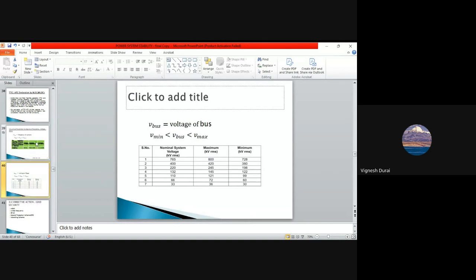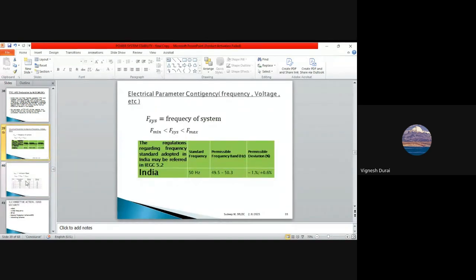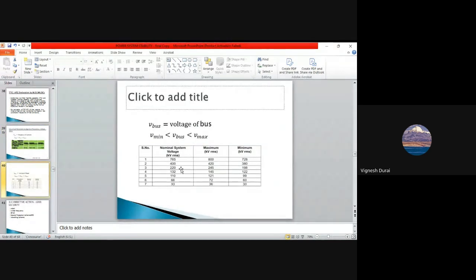This is what the IEGC is following. And in a 220 kV system, you have a 10% margin. It means that you can operate from 245 to 198. Anything is okay. If it is going below 198, again you have to take action. That is the job of a grid operator. We should not let the system go below or above the permissible limit, that is what we have to analyze and decide.